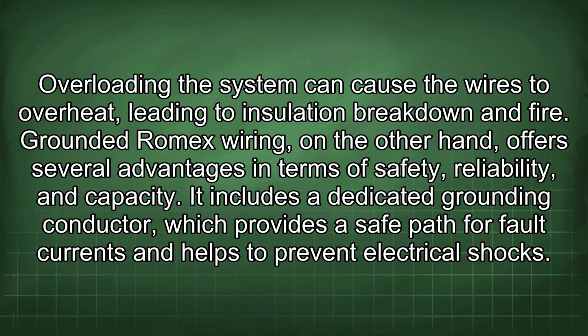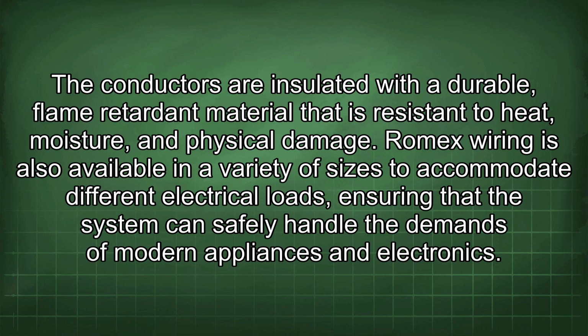Romex wiring, on the other hand, offers several advantages in terms of safety, reliability, and capacity. It includes a dedicated grounding conductor, which provides a safe path for fault currents and helps to prevent electrical shocks. The conductors are insulated with a durable, flame-retardant material that is resistant to heat, moisture, and physical damage. Romex wiring is also available in a variety of sizes to accommodate different electrical loads, ensuring that the system can safely handle the demands of modern appliances and electronics.